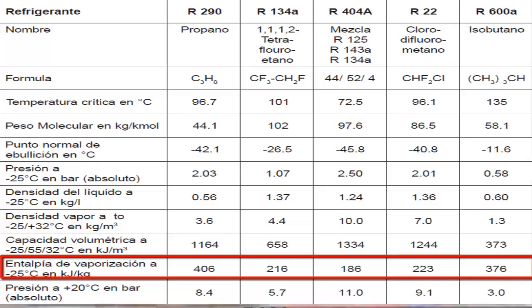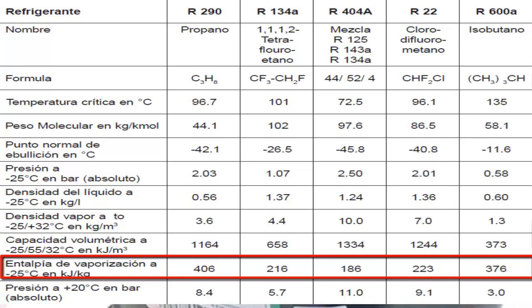In contrast, R290 is less dense, which means that much less quantity of R290 grams will flow through the compressor. However, each gram of R290 has greater cooling power, compensating for its lower density. A compressor with R290 handles fewer grams of this gas, but each of these grams has a greater cooling power than a gram of R22.